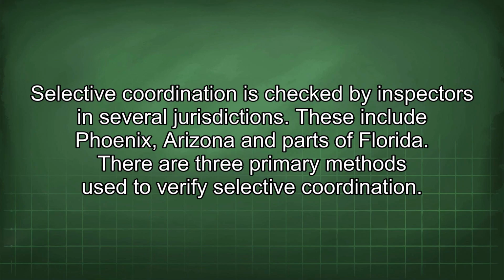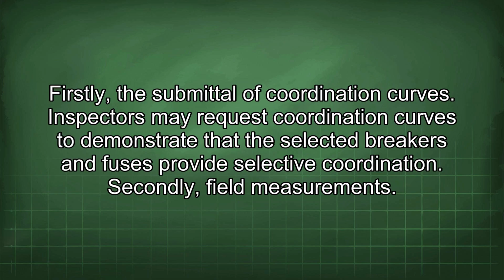Selective coordination is checked by inspectors in several jurisdictions. These include Phoenix, Arizona, and parts of Florida. There are three primary methods used to verify selective coordination. Firstly, the submittal of coordination curves. Inspectors may request coordination curves to demonstrate that the selected breakers and fuses provide selective coordination.